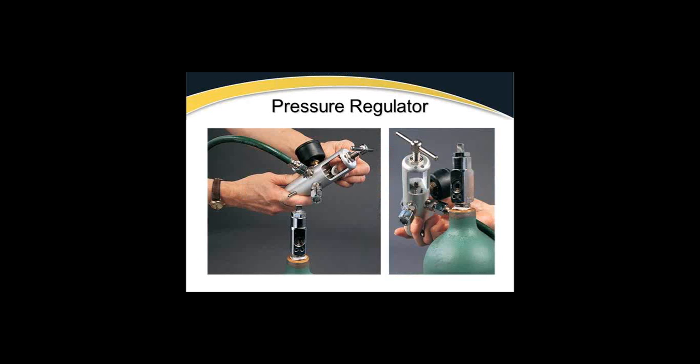And here's the picture that I was exactly talking about. The 2 and 5 pin system. They're putting a gasket over the oxygen inlet for the regulator, and then you'll slide that down over the top of the bottleneck and secure it with the thumb screw.